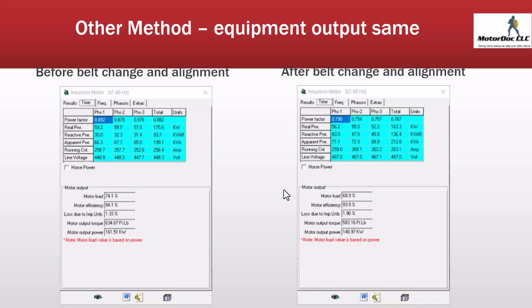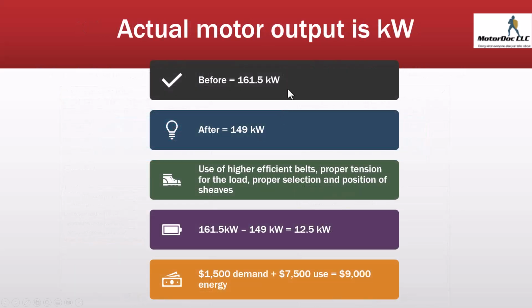and just a slight change in the sheave. So beforehand, the input was 175.6 kilowatts. Afterwards, it dropped down to 163.3, basically almost 12 kilowatts. Now, that's a direct measurement that includes the effects on the system. So I can take that and say 12.5 kilowatts. Take a look, and that's $9,000 worth of energy.